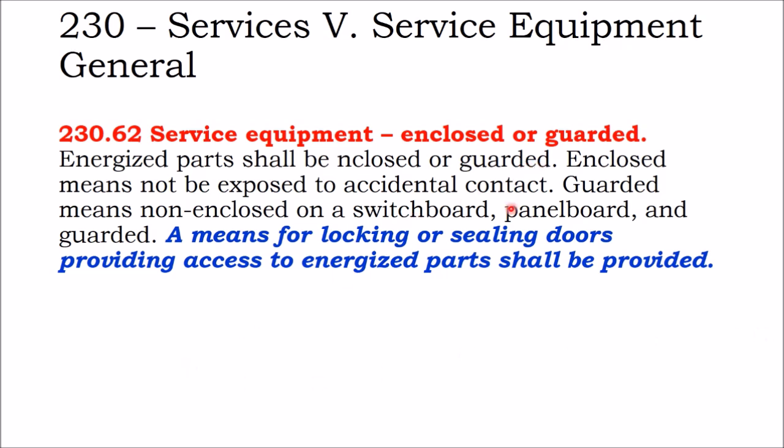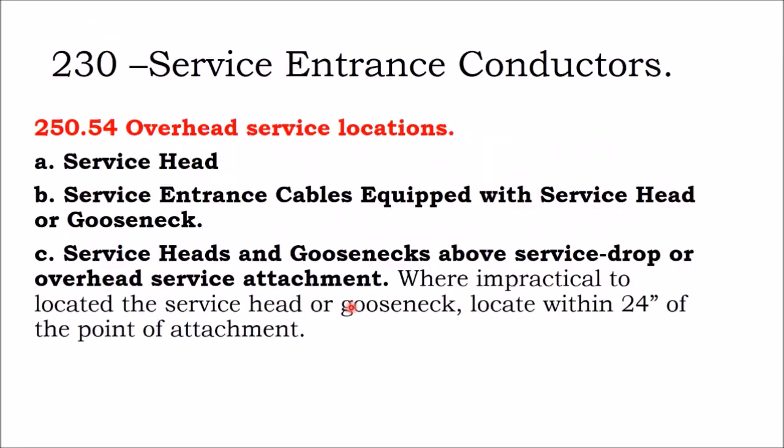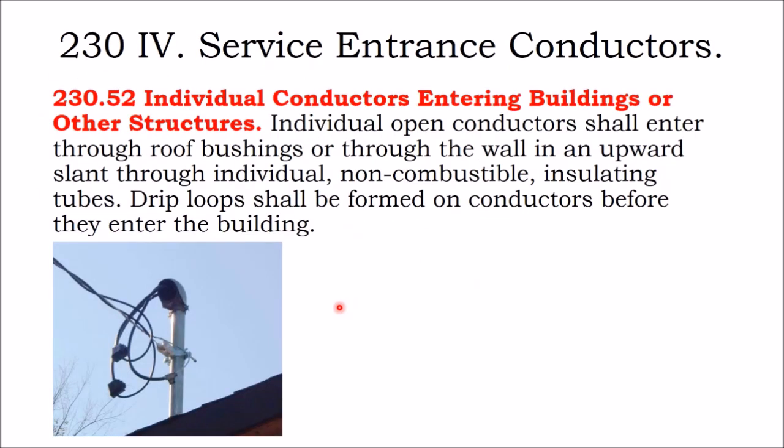I remember one day on a job site where the utility had come to wire up a new service, and we had run our conductors up, but we were still working on the inverter room. The utility came out to hang the transformer, and they went ahead and hung their wires as well, but they did not perform the tap. They just taped their utility service entrance conductors up and left them hanging.